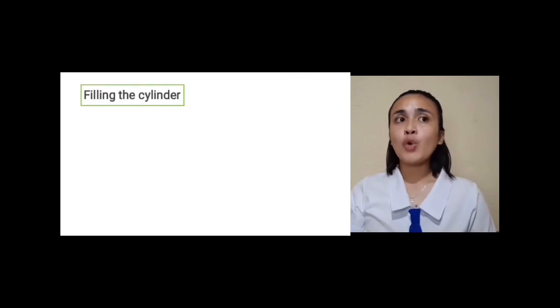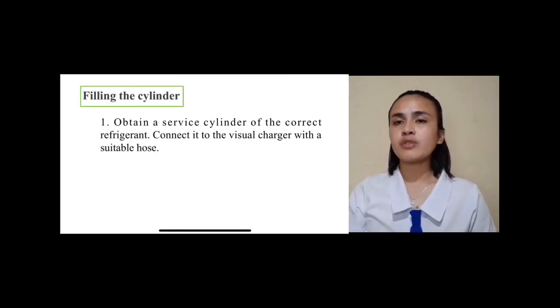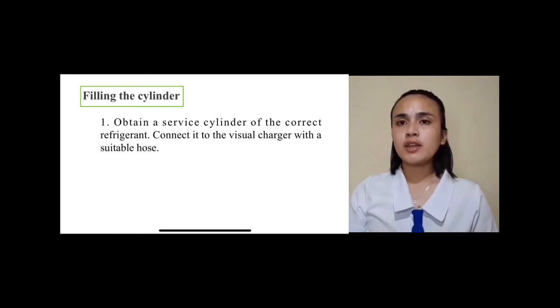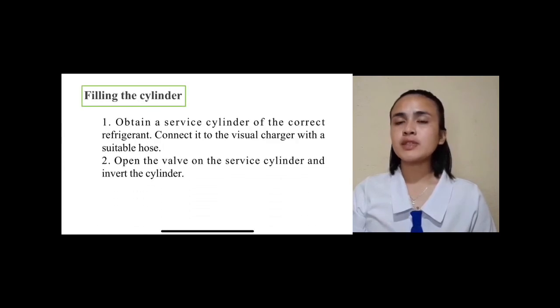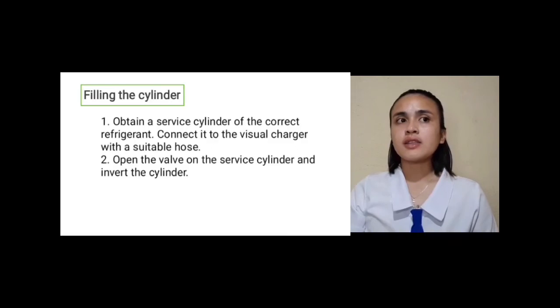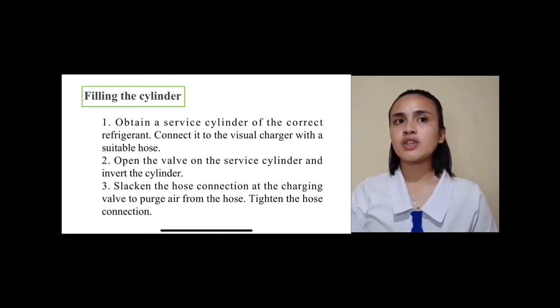Number 1. Obtain a service cylinder of the correct refrigerant. Connect it to the visual charger with a suitable hose. Number 2. Open the valve on the service cylinder and invert the cylinder. Number 3. Slacken the hose connection at the charging valve to purge air from the hose. Tighten the hose connection.